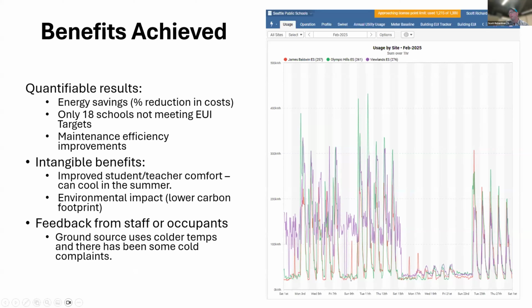Here is an example. You guys mentioned Sky Spark. Here's an example of James Baldwin, Olympic Hills, and Viewlands on Sky Spark. Olympic Hills is an individual heat pump per classroom. James Baldwin and Viewlands are the water heat pump systems. All three of these are ground source. But you see here Olympic Hills in green does have the peak. This is where you start talking about peak demand energy. If your local utility says over 300 kilowatt hours, you're going to get a new increased rate. You want to look at this system and make sure whatever's happening here is mitigated.